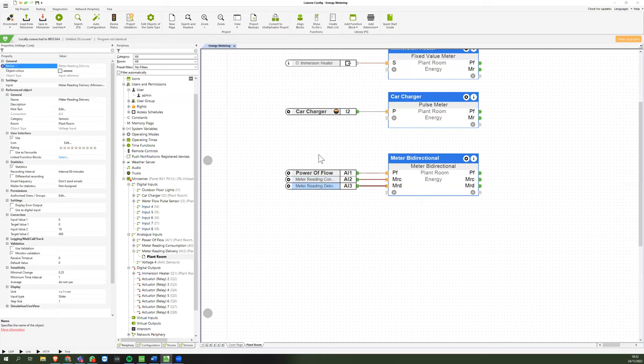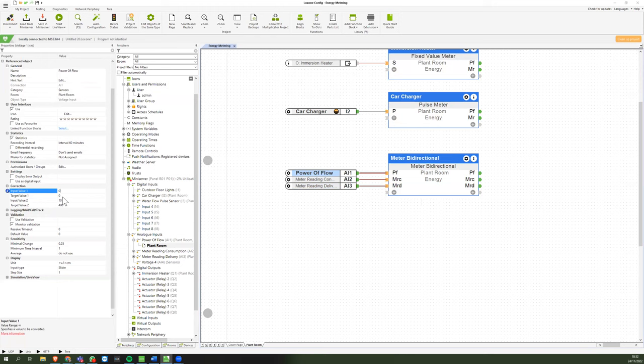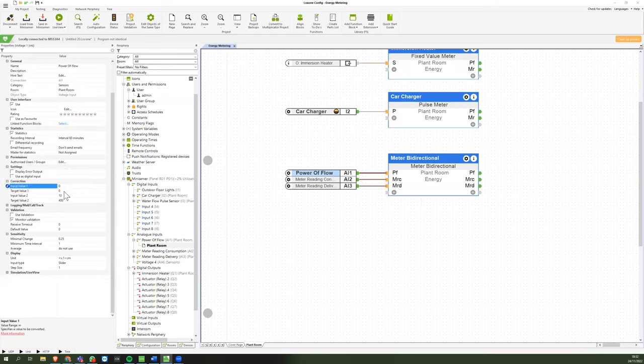There we go. And I also want to map them because, as you know, currently my 0 to 10 volt sensors are just saying 0 to 10, but we can obviously do more. We want to do more. So let's do that. If we go to, let's say, power flow, currently the sensor's input values are between 0 and 10, and then the target is mapped between 0 to 10. So if it gets a 0 to 10 input from the block or from the sensor, it's going to map it to something.